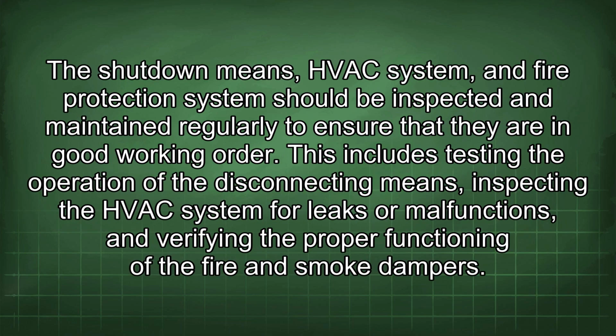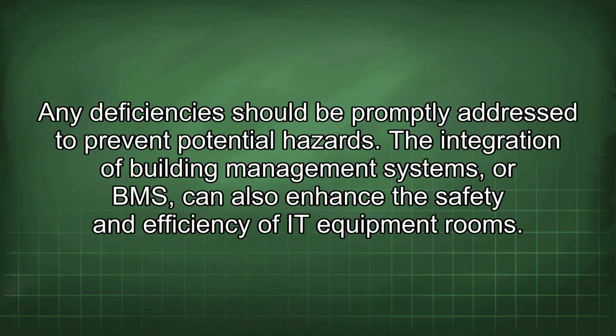The shutdown means, HVAC system, and fire protection system should be inspected and maintained regularly to ensure that they are in good working order. This includes testing the operation of the disconnecting means, inspecting the HVAC system for leaks or malfunctions, and verifying the proper functioning of the fire and smoke dampers. Any deficiencies should be promptly addressed to prevent potential hazards.